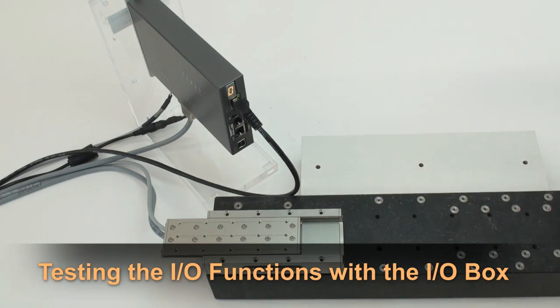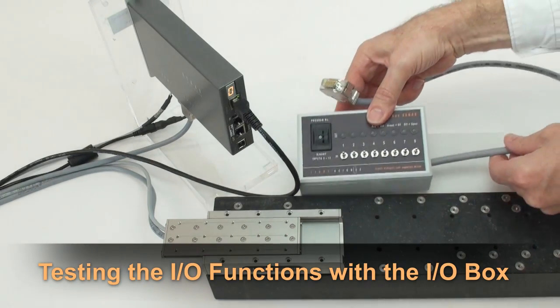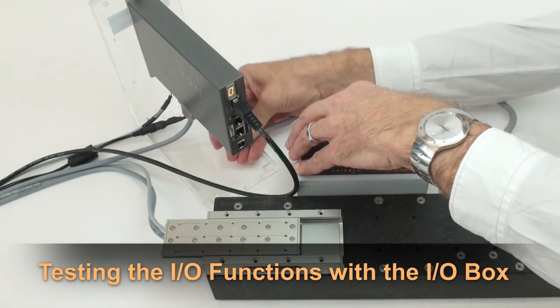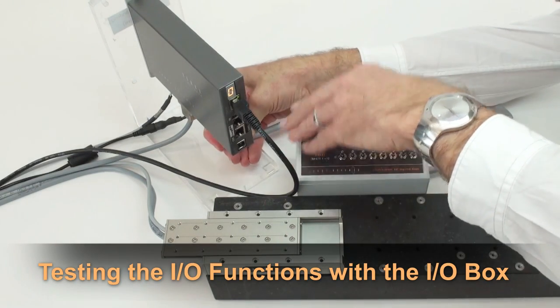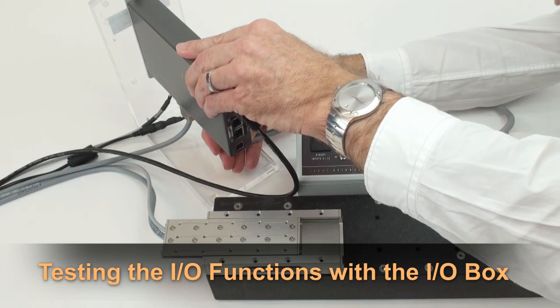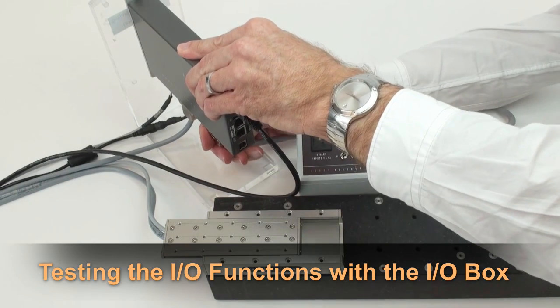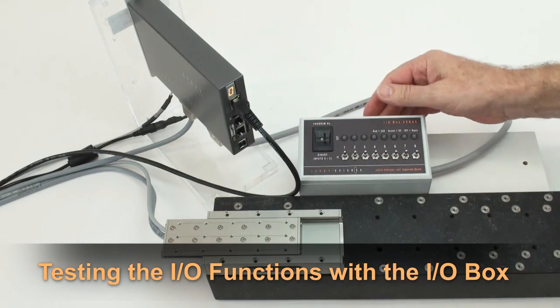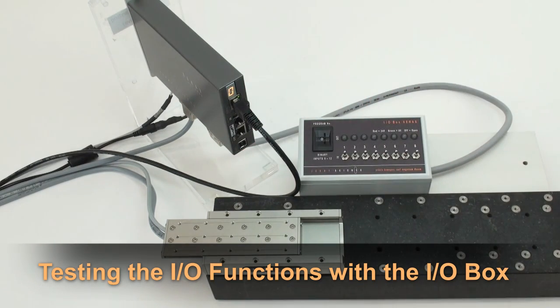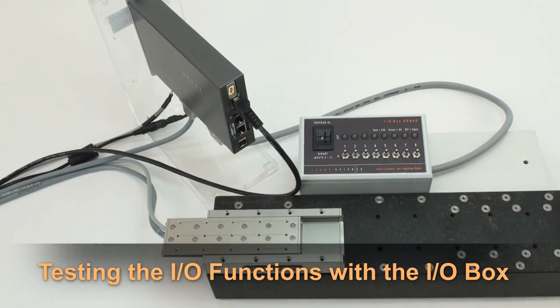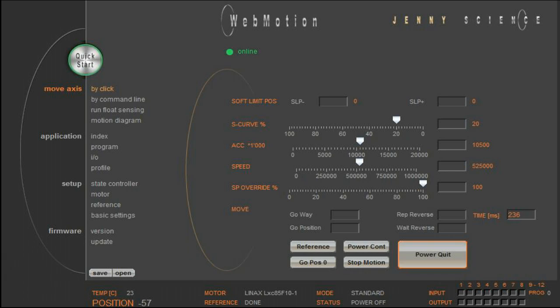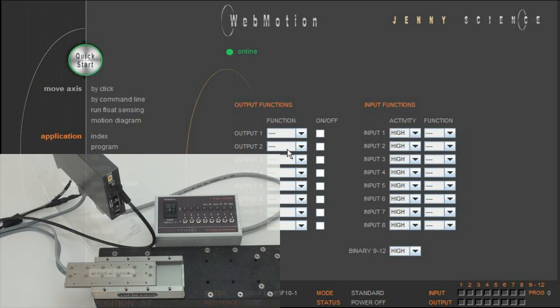The XENAX servo controller has 12 digital inputs and 8 digital outputs for the user. In addition to the standard I.O. functions for sensor check or for actuator control, it is possible to assign complex functionalities or programs to this digital I.O. interface. The outputs are flexibly configurable via software as a sink driver 0V or source driver 24V.